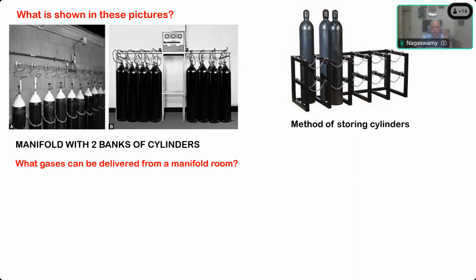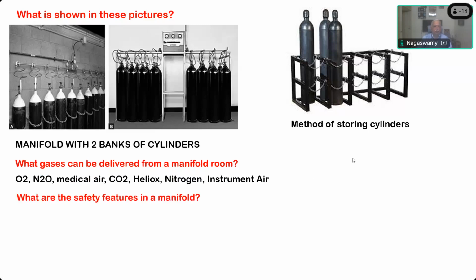But in Western countries, they use heliox also. So oxygen, nitrous oxide, medical air, carbon dioxide, heliox, nitrogen, and instrument air. That is for orthopedic surgeons when they want to use the drill, or neurosurgeons when they want to use the burr. For all these things, you need non-medical air. It is called instrument air. All these things can be delivered from a manifold room.